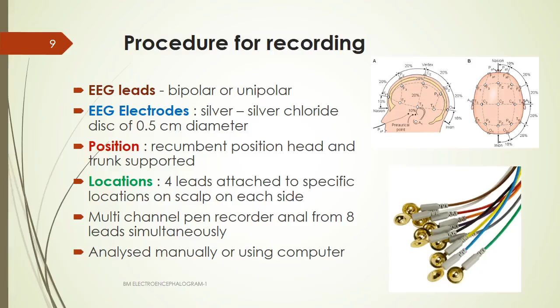So here also the electrodes are there. The patient will be in the recumbent position, and 4 leads are attached to specific locations of the scalp on each side. Totally, a multi-channel pen recorder will record 8 channels simultaneously. There is the 10-20 system, and more systems are also there. After getting these potentials through these pens on the graph, it can be analyzed manually or using a computer.